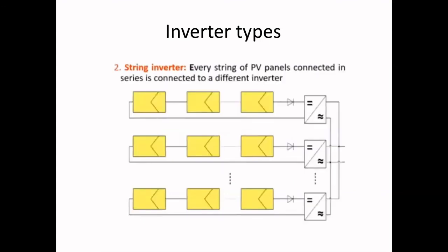In this type of inverter, we'll use one inverter for a single array. So for 3 panels, we are connecting an inverter. So we'll have more SCADA points. So we'll have to connect more MPPT controllers, and we'll have to look into the reactive power generation of each and every module, so the cost invested will be increased in this string inverter, but the efficiency will be high and we won't get complete interruption. Instead, we will get one or two arrays interrupted so that the output will not be mostly affected.